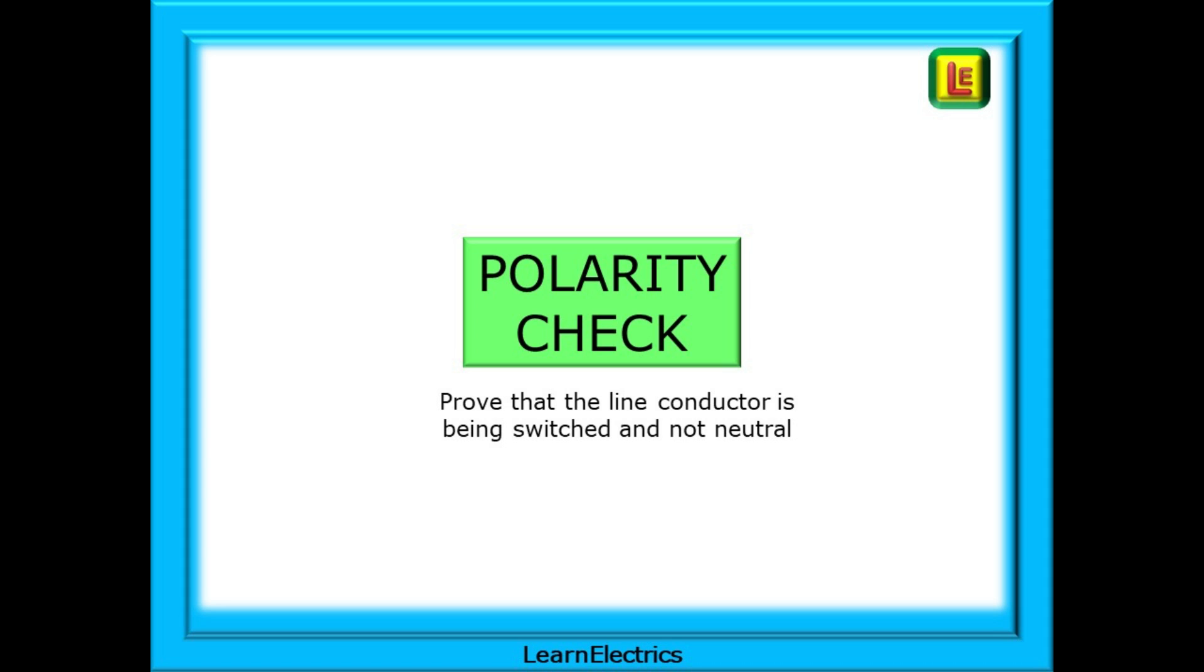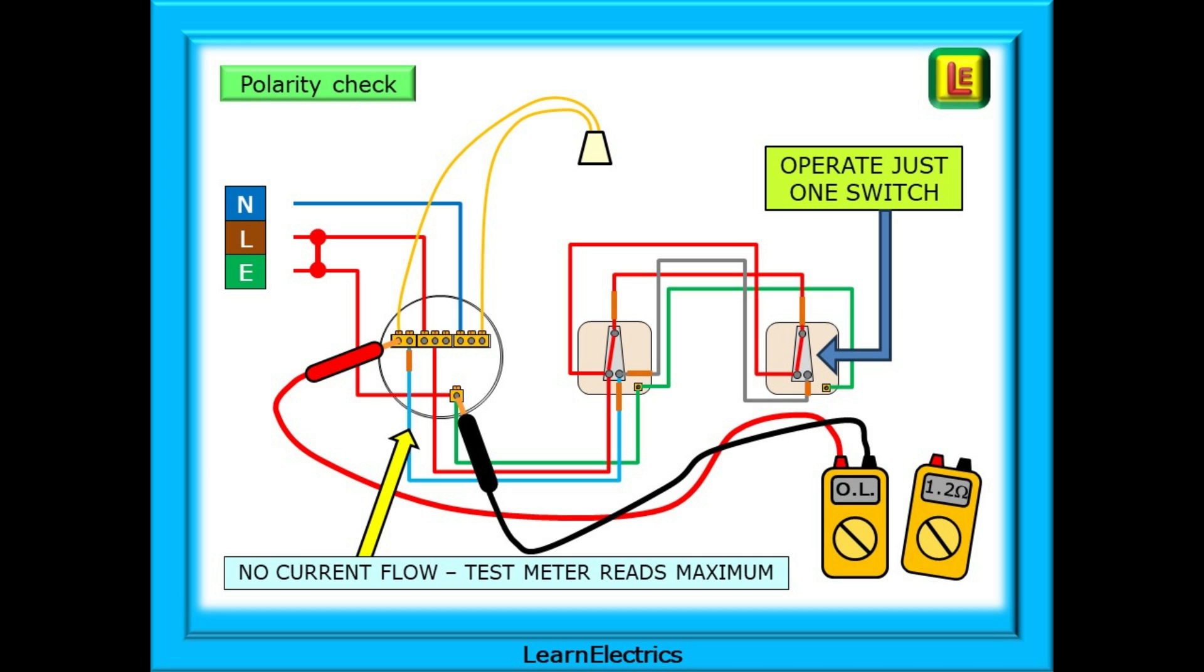A polarity check can be carried out at this stage. According to the wiring regulations test sequence, this is carried out later, but as everything is set up for a polarity check, do it now. Simply operate the first switch and test and the meter should show a maximum reading shown as OL on my meter. Operate the second switch and the meter should display a low ohms reading again. This proves that the line conductor is connected to the switches and is operating correctly. Switching polarity is correct.